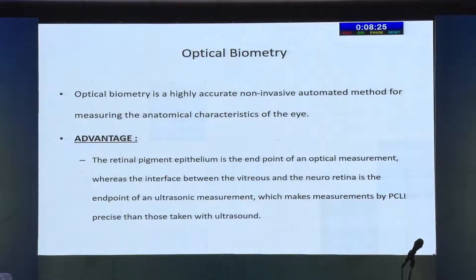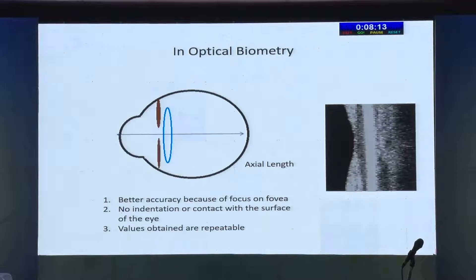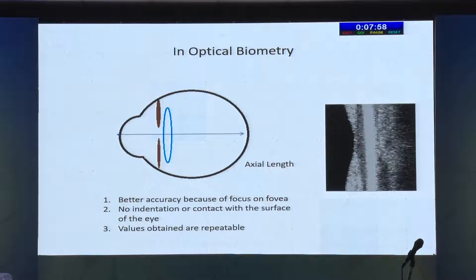Optical biometry is a highly accurate, non-invasive, automated method, and we all know axial length comes out very, very accurately. But is that the only point? In optical biometry, because you're looking at fixation of the patient into the light source, you most probably are getting the evaluation right through the fovea. So your axial length is not only accurate because you're using light instead of sound — you're also getting it along the visual axis perfectly.